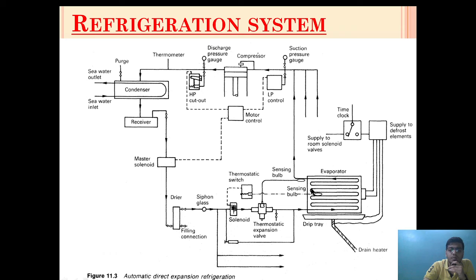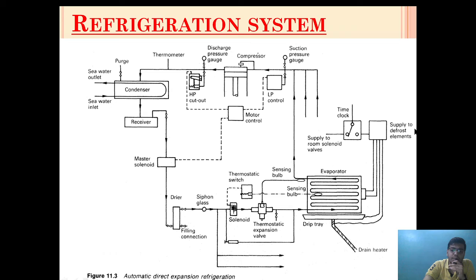As the refrigerant flows in the evaporator, it will extract the heat, making the surrounding temperature of that area get cooled. As it gets cooled, the refrigerant boils off, converting from low pressure liquid refrigerant to gas form. A defrost element is also provided so that from time to time the evaporator coil can be defrosted, to prevent unwanted accumulation of ice over the surface so that a good amount of heat transfer can always take place.